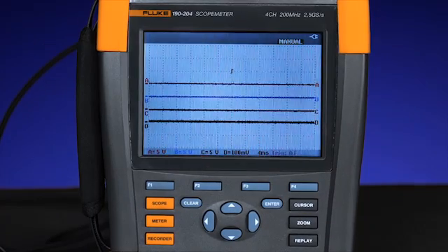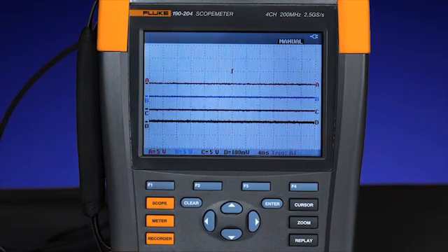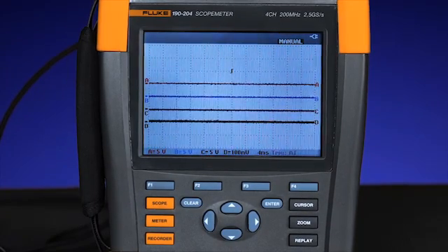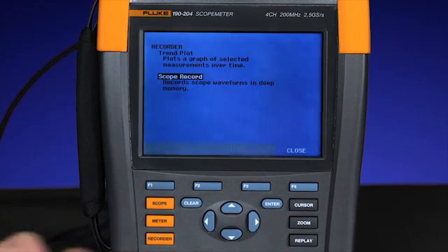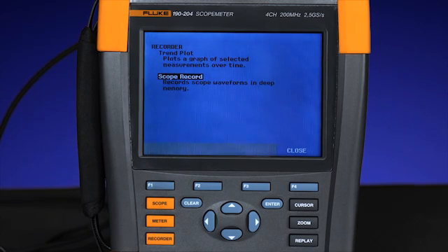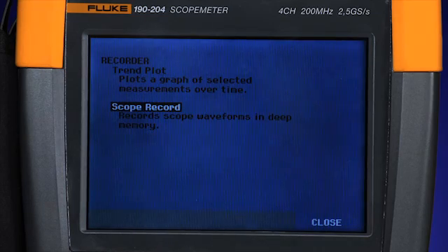In order to capture the waveforms on the four inputs at the startup sequence of the machine, we'll go in and use the oscilloscope in the scope record mode. The scope record mode will capture the high resolution digitized waveform over an extended period of time. It can capture an event of recorded waveforms for as long as 24 hours.